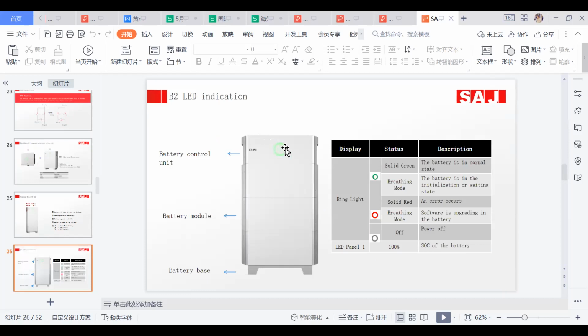And we also have the BMS box, the battery control unit. The light shows the working mode, the working conditions of the batteries, and the number within the ring shows the remaining SOC. And for our batteries, there is a battery base. It happens sometimes that after I upgrade the software of the BMS, the ring is red and in breathing mode. The customer called me that there is an error in the system, but it is normal after upgrading when the ring is in breathing mode.